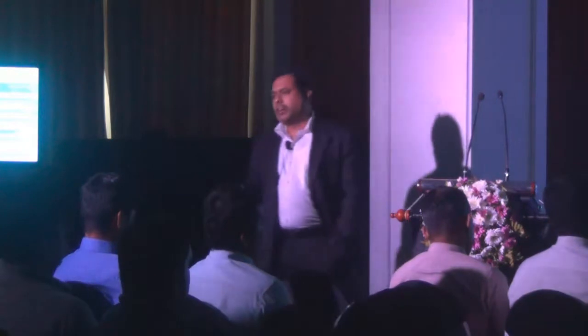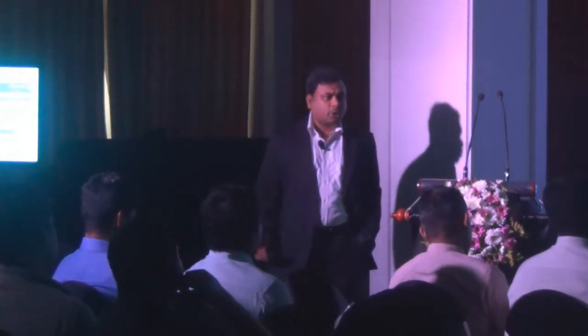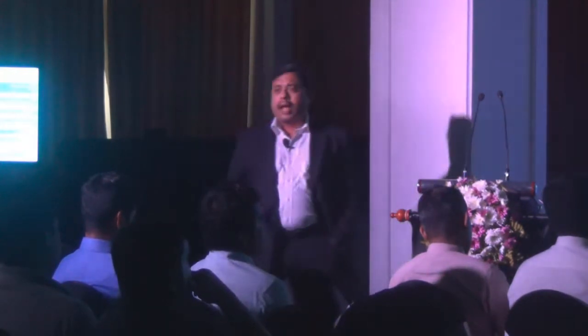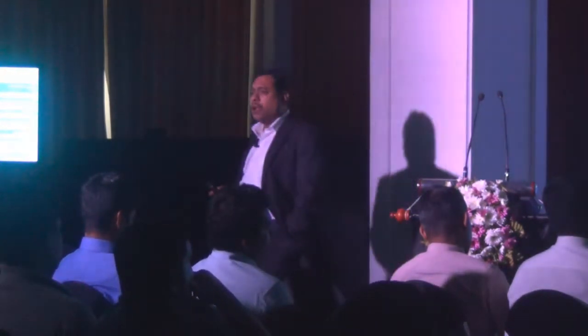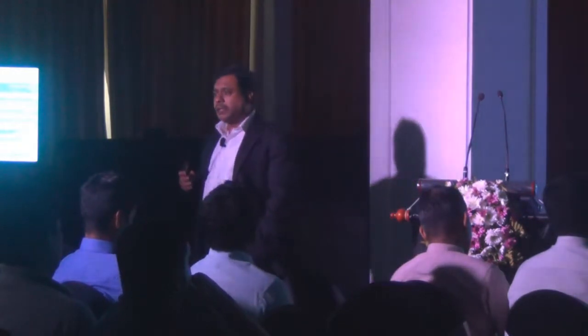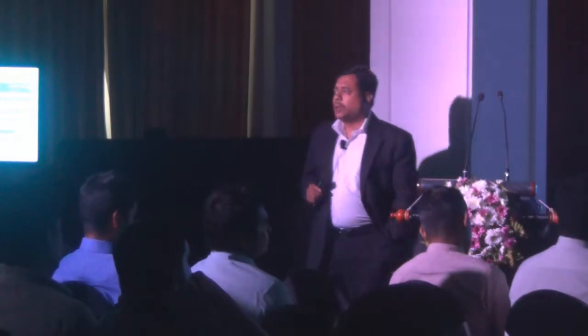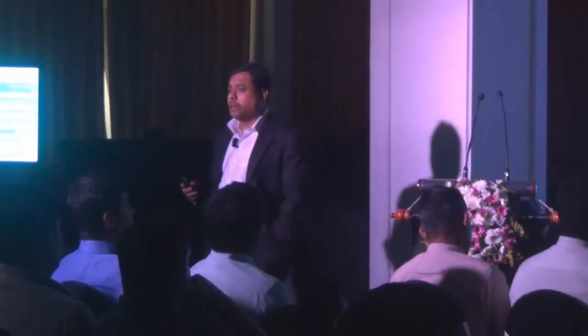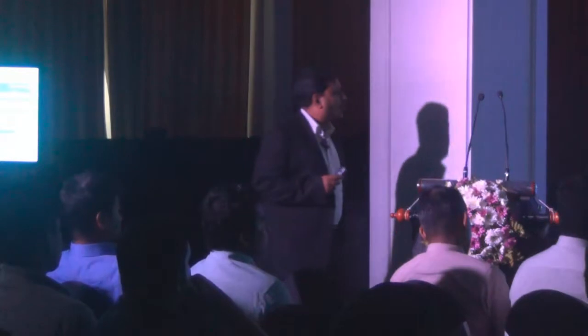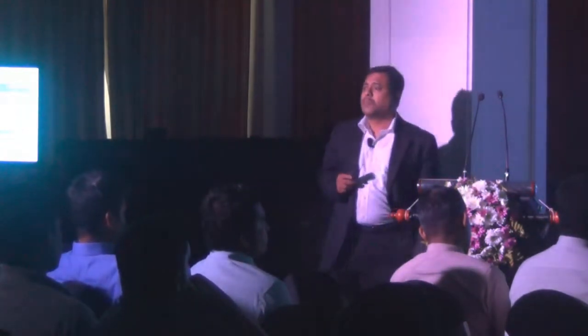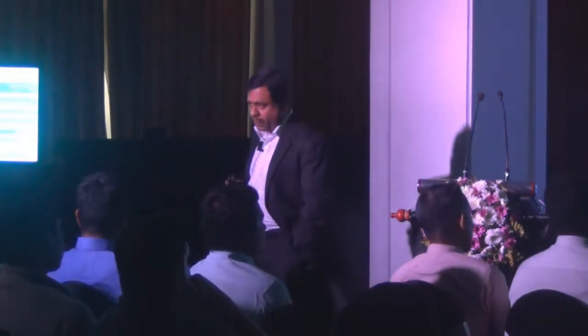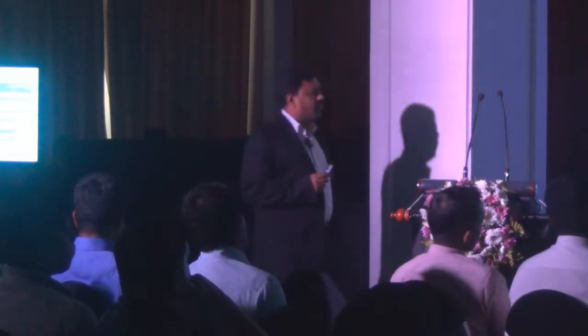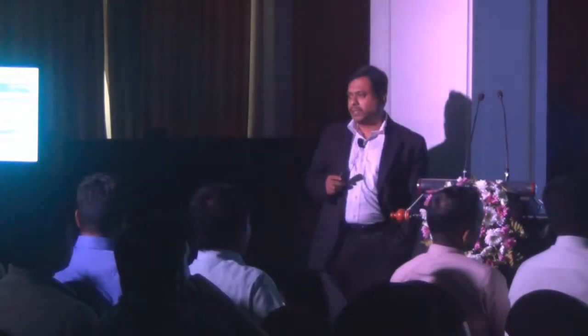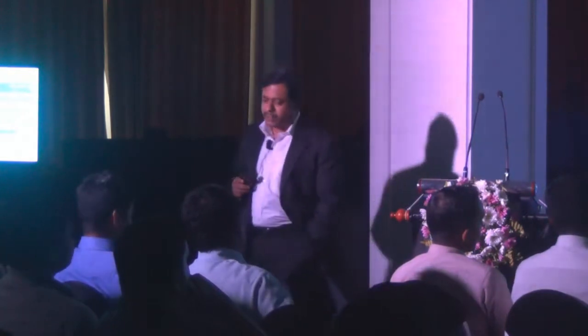Now comes the Trinergy model of UPS system. This is completely a state-of-the-art solution. This Trinergy model has 3 types of modularity. One is the vertical modularity, the second is the horizontal, and the third is the orthogonal. So with the UPS system, you can connect 1.6 megawatt in each input-output box, and this comes with a 200 kilowatt module core. And this has a very, very high efficiency of 98%, and in eco mode it operates at 99%.